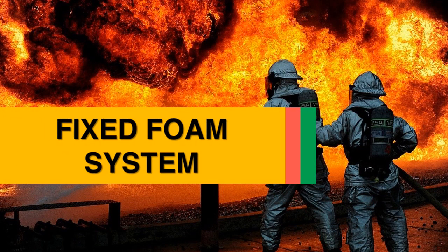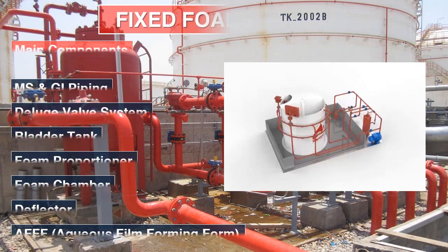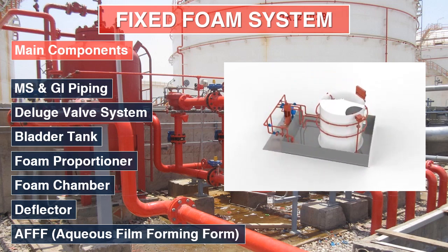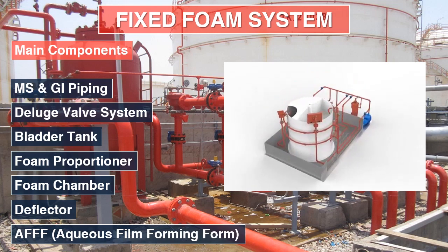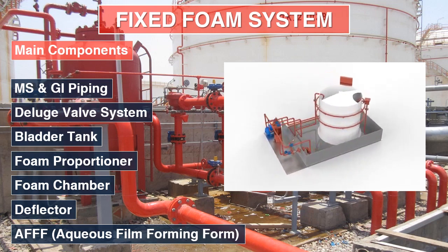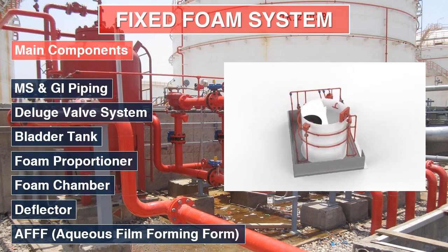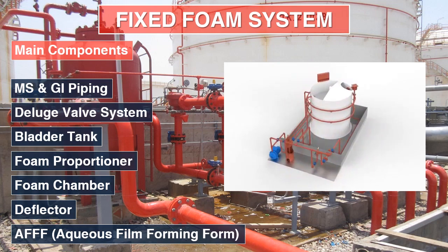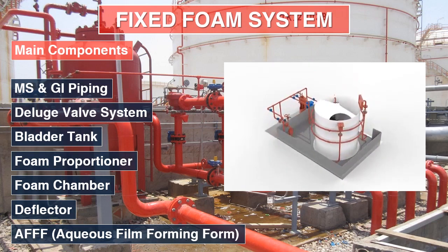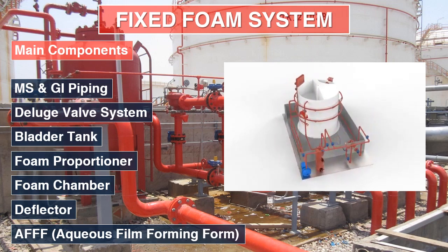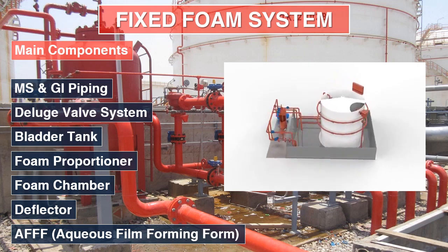We will see the fixed foam system, its elements, and working principle. Foam system is used for extinguishing fires involving flammable liquids. Foam is lower in density than flammable liquids. It is a blanketing and cooling agent produced by mixing water and foam concentrate. It flows freely over a burning liquid surface and forms a tough, air-excluding continuous blanket that seals volatile vapors from access to air. The system employs a bladder tank proportional system for induction of foam concentrate.